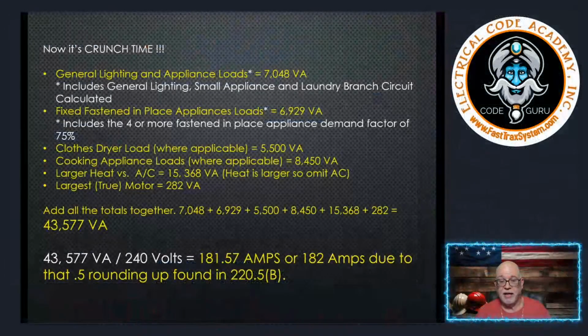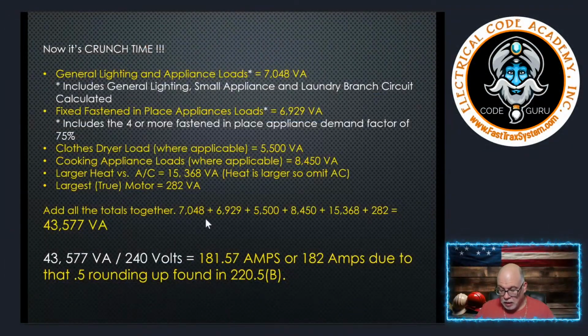Here we've got to focus. You could go running over to 310.16, folks, and simply go to the 75-degree column because of the terminal and temperature limitations of 110.14(C), and say, I'm just going to find a conductor that can handle 182 amps and be done with it. But there's something you have to remember. This is not an exception.